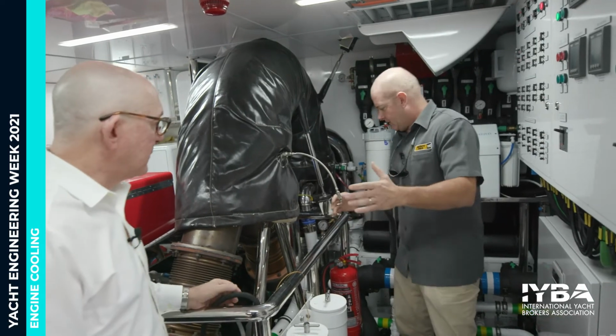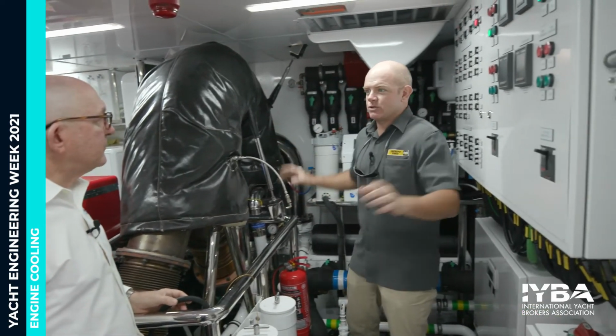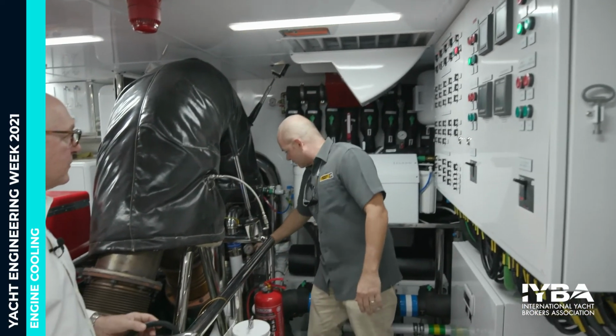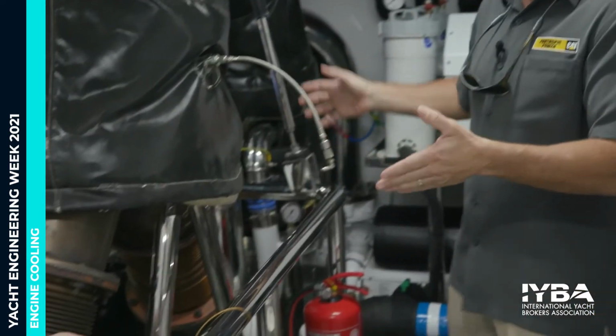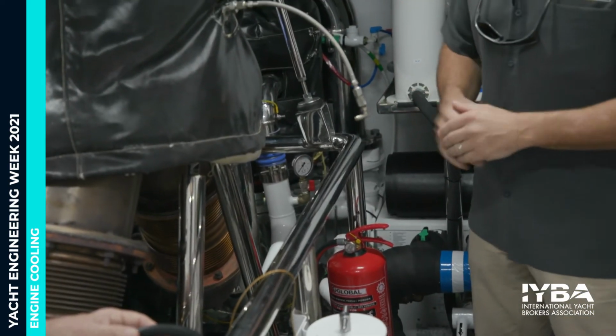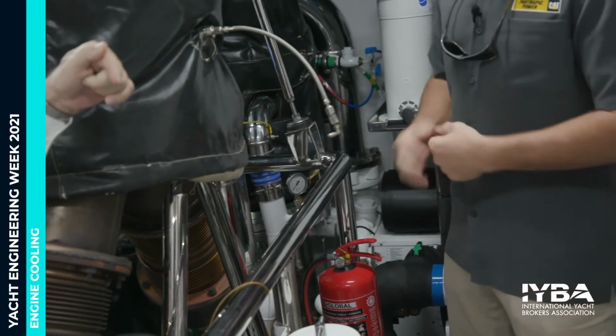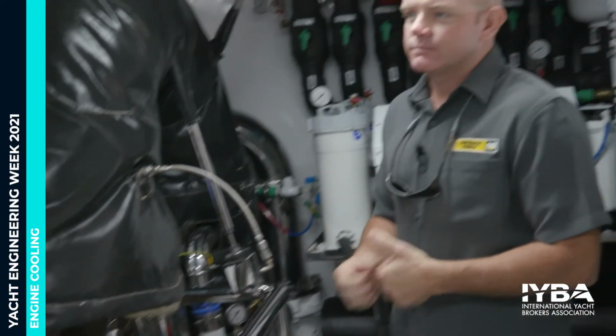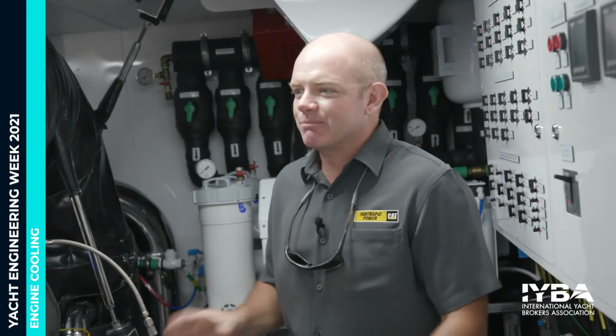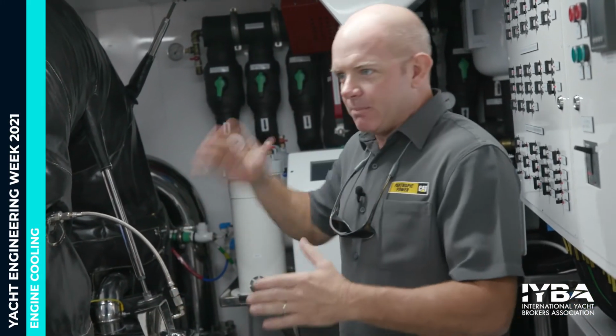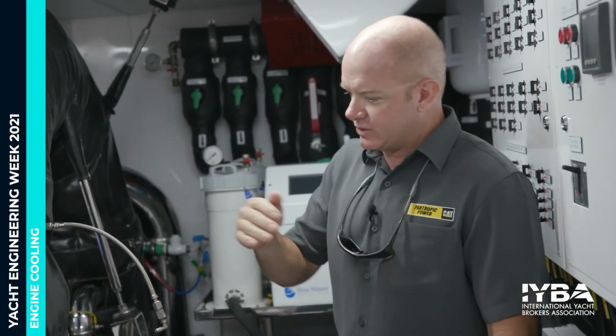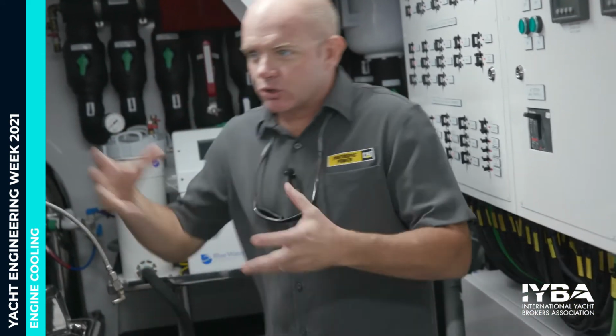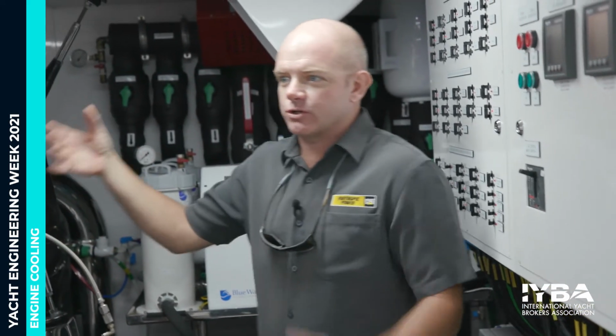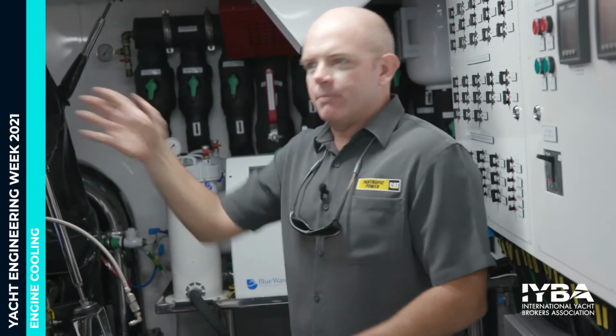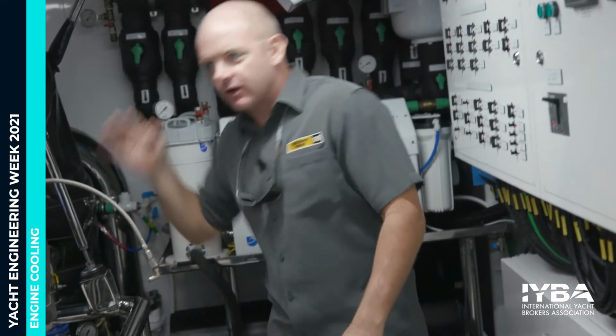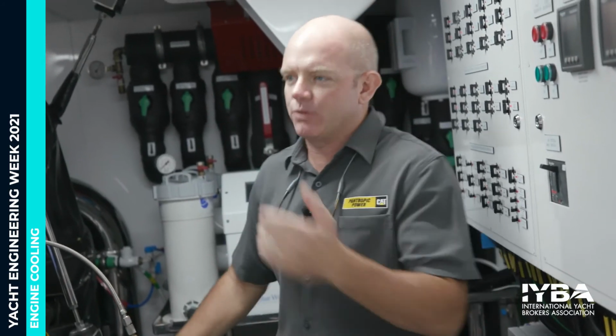When everything's brand new and clean, you can see where your restrictions are going to be in the system, and you make note of that, maybe even put an indicator on the gauge so it's easy to tell if the pressure's increased or decreased. You put a little tape mark on it, and then you've got a baseline to move off of. So down the road, as the transmission cooler gets dirty, or the heat exchanger gets growth on it, or the impeller wears, you'll see that pressure change, the restriction's going to increase.